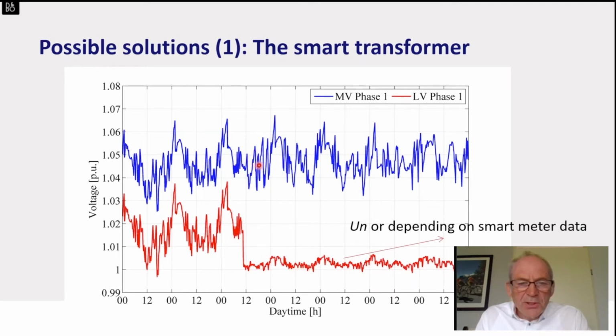The variations in the medium voltage network, shown in blue, are something you don't have anymore when you switch on the smart transformer. That means the plus or minus 5% kept for the medium voltage can also be spent in the low voltage network. So the full plus or minus 10% variation can be utilized in the low voltage network.